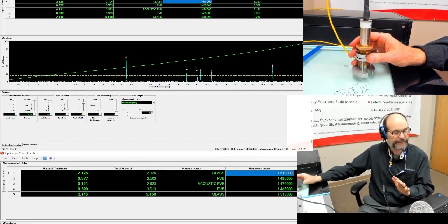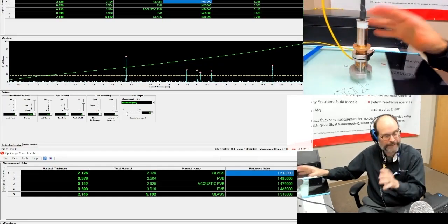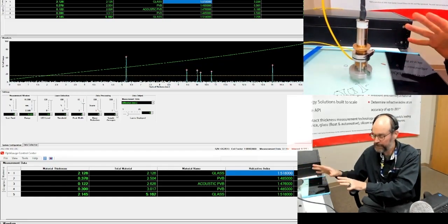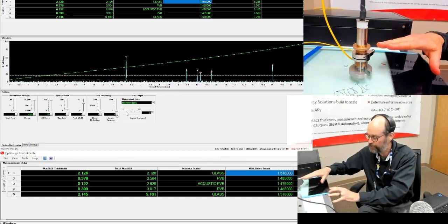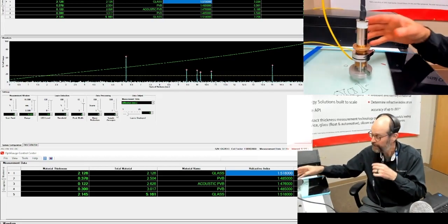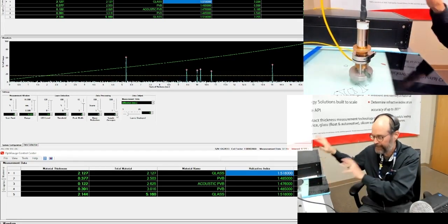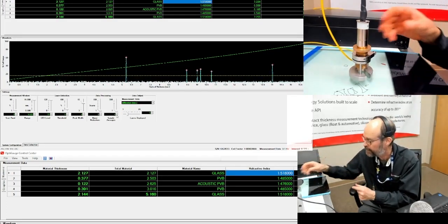Moving on, there is something you have to keep in mind. We're talking about setting the height, but normally we're also concerned with tip and tilt, right? This probe kind of takes that out of the equation. You don't have to do it, you just do it by dead reckoning, let's call it.